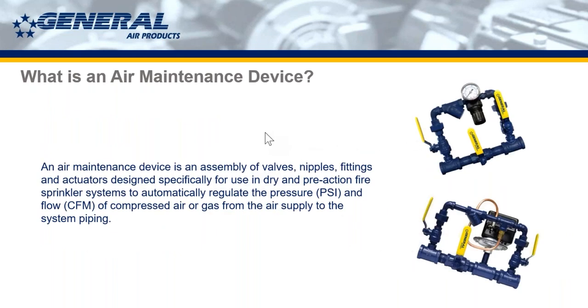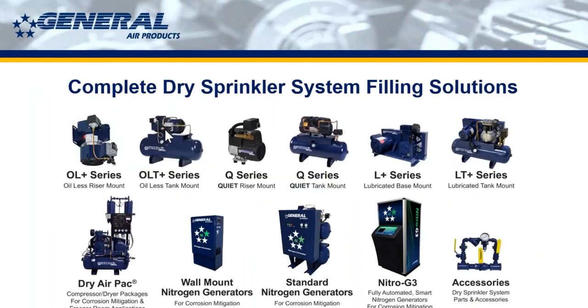An air maintenance device is an assembly of valves, nipples, fittings, and actuators designed specifically for use in dry and pre-action fire sprinkler systems to automatically regulate the pressure and flow of compressed air or gas from the air supply to the system piping. So that's, I don't know, usually I don't just go reading slides, but there's no better way to say that, so we just do it. But that's what an air maintenance device is.